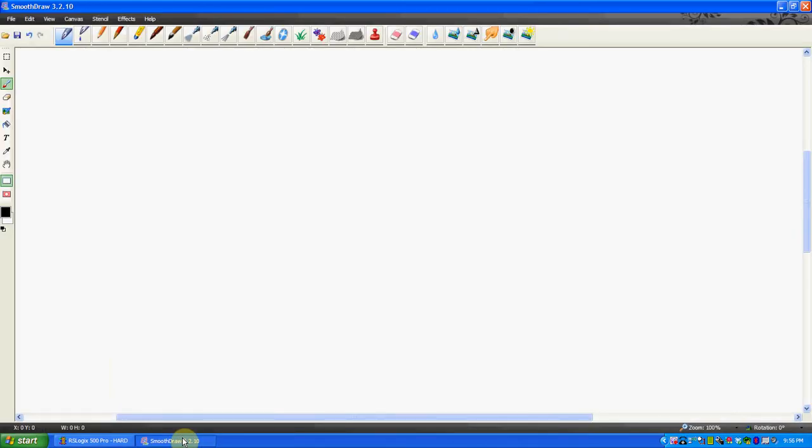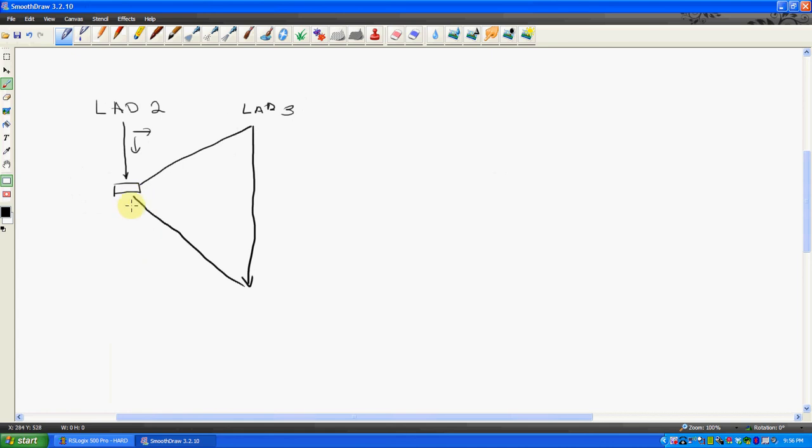To give you an idea of how that would look pictorially, if I started out with ladder 2, it would scan ladder 2. This is doing that whole left to right, top to bottom thing. When it gets to a command that says run a subroutine, it jumps out, and what I just created was ladder 3. That's badly written, but ladder 3.